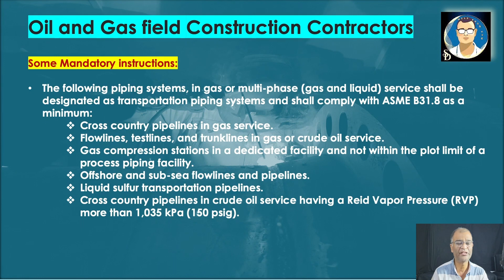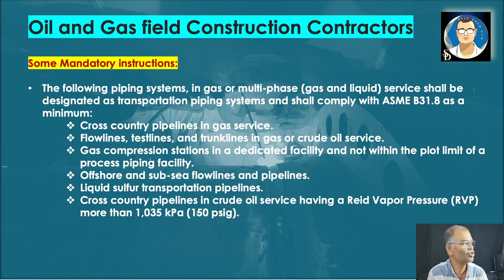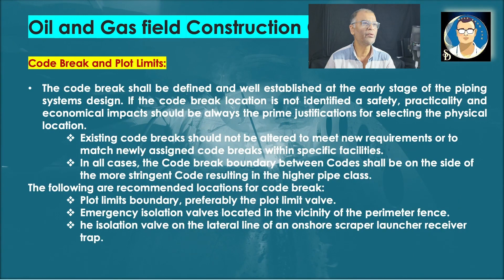Piping systems in gas or multi-phase gas-oil-liquid service shall be designed per B31.8. This includes cross-country pipelines in gas service, flow lines, test lines, and trunk lines in gas and crude oil service, gas compression stations in a dedicated facility not within the plot limit of a process piping facility, offshore and subsea flow lines and pipelines, liquid sulfur transportation pipelines, and cross-country pipelines in crude oil service having a Reid vapor pressure more than 1035 kPa (150 psi).